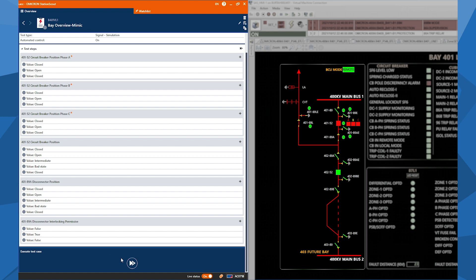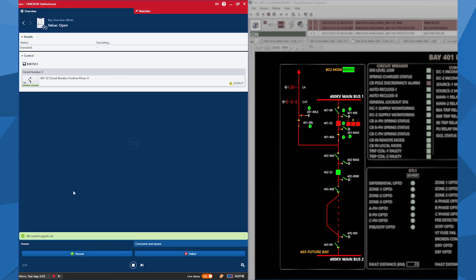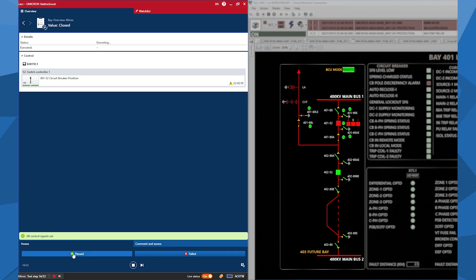So to run the test, I just click on the execute test case and observe from the HMI screen. So now I see that the circuit breaker phase A is closed. I see also here A, B, C. These are the single position phases of the circuit breaker. It's closed. So I will follow a closed-open-closed cycle, and you see that the screen now it's opened. Okay, now phase A is closed, and I see that it's closed again. So in the phase B, I see that it's closed. Yes, that's true. Now it should be opened. That's fine, and it's closed. One after other, we can imagine that all the switch positions will be red that shows us they are tested, and at the end I will have the mimic diagram all the closed positions that would mean that I tested each and every position.